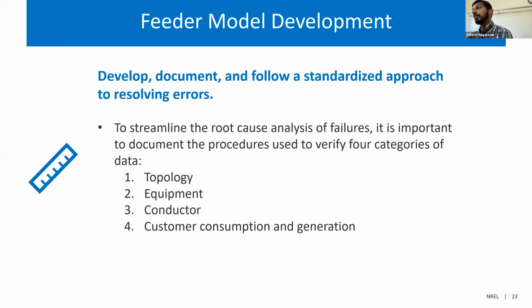The issue may be coming from topological errors, which means your GIS data can be wrong. It could be due to a wrong equipment database - meaning the database you have for transformers or regulators may be wrongly updated, outdated, or erroneous for whatever reason. Maybe you have wrong conductor information, where impedances are wrong. Or it may be that your customer consumption and generation data is wrong, meaning your load allocation is wrong. In the next few slides, we'll get one level deeper into each of these so we all have a clear understanding.